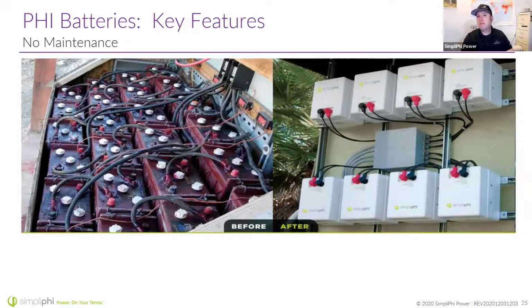We were able to come in, and the picture on the right is a battery bank that has just as much energy capacity, in kilowatt hours or amp hours, and just as much discharge power rating. It's able to support loads just the same as the picture on the left. The left picture was probably only being cycled down to 50% state of charge, and sized for a discharge at C over 20. The picture on the right can be discharged all the way, and at C over 2. So drop-in lead acid replacement is very powerful to do, and it's great for building relationships with customers, because inevitably you can also sell new components down the road.